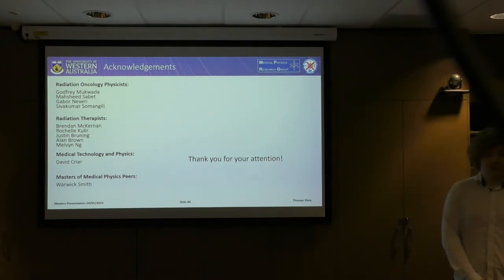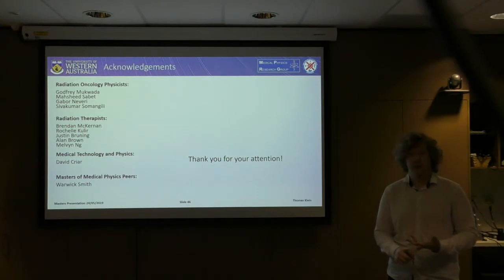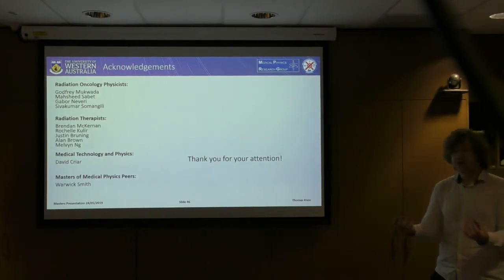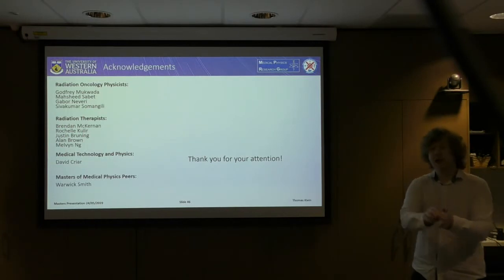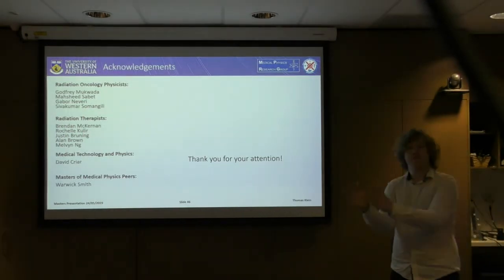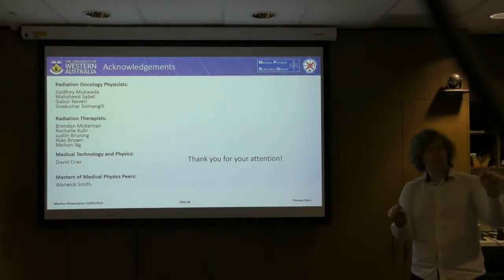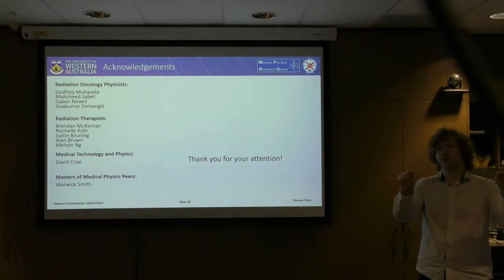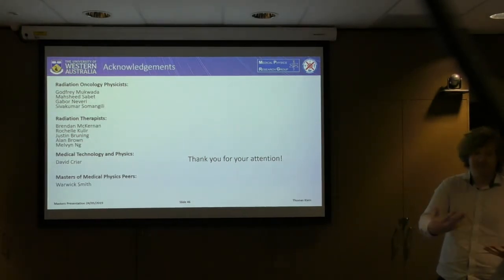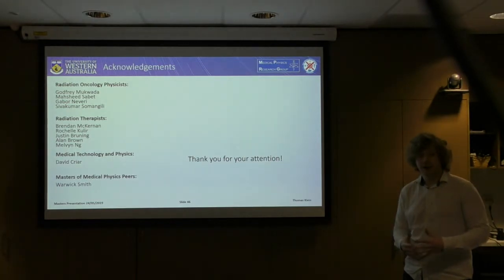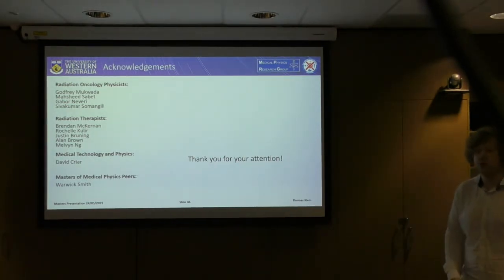Question: Based on your gamma index comparison, what would you say are the limitations? Response: One major limitation of the gamma index is that when a point fails, you don't know whether it's failed because it exceeded the dose tolerance or the distance tolerance. The user specifies a dose and a distance; if a point passes, it found another point in the reference distribution within the dose tolerance within the specified distance — so a point doesn't have to be within 3% of the exact same point, it could be within 3% of a point 1mm away. In our distributions it was fairly obvious that points failed due to dose being hot, but otherwise it would have been very difficult to distinguish.